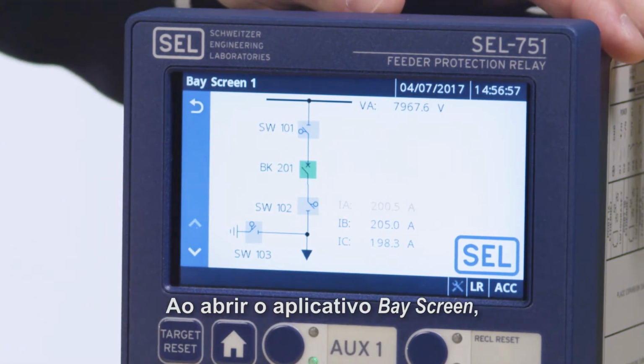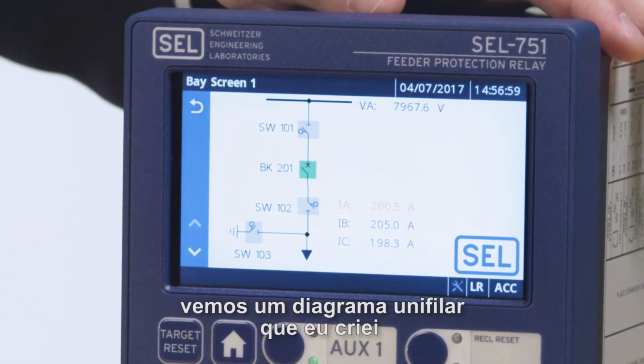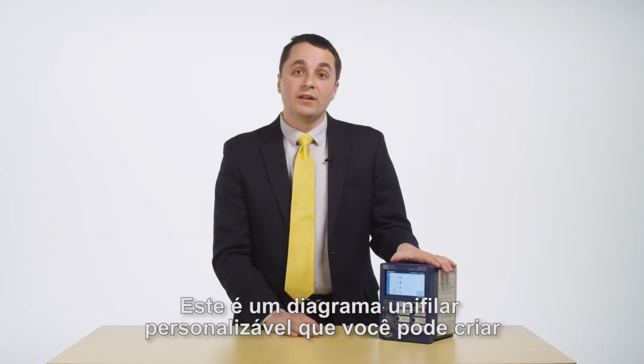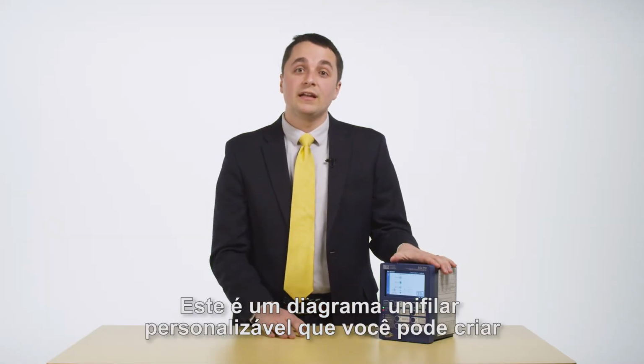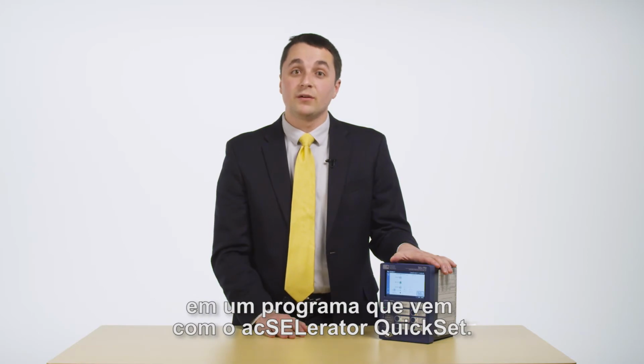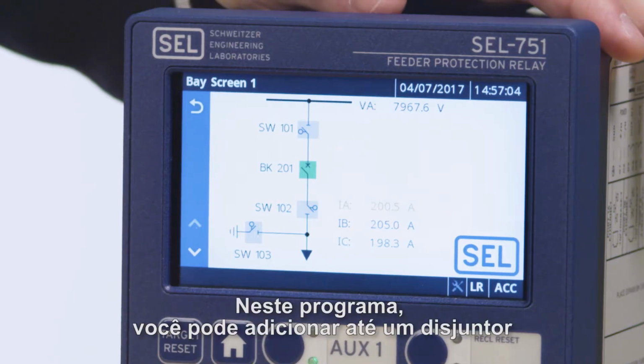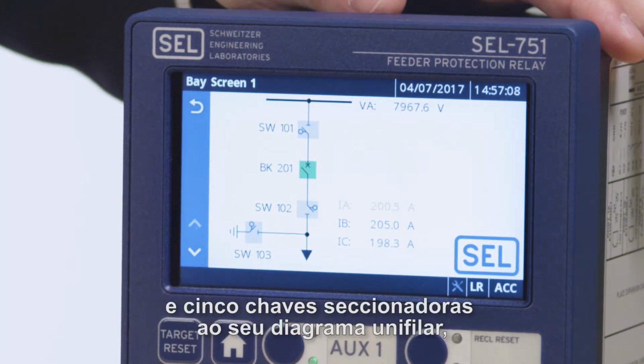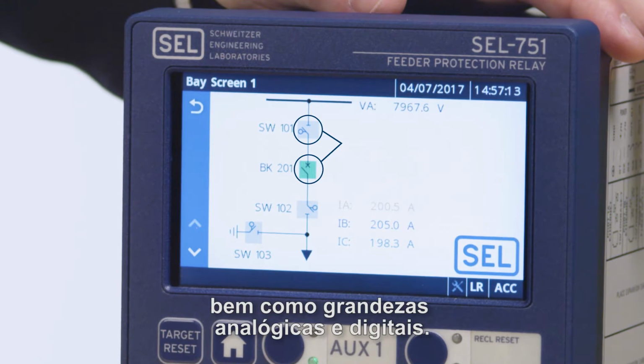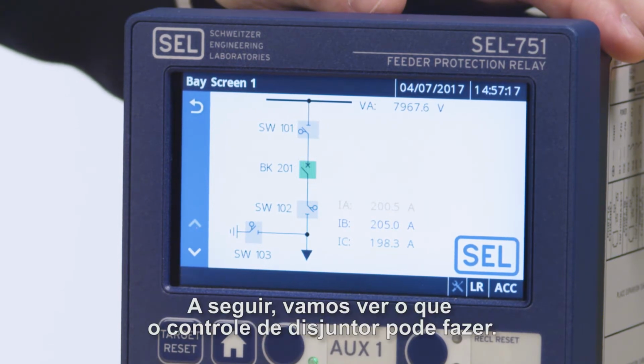When I open the Bay Screen application, it shows a one-line diagram that I have created. This is a customizable one-line diagram that you can create in a program that comes with Accelerator Quickset. In this program, you can add up to one breaker and five disconnect switches to your one-line display, as well as analog and digital quantities. Next, we're going to take a look at what the breaker control can do.